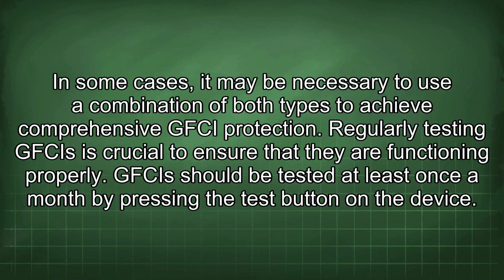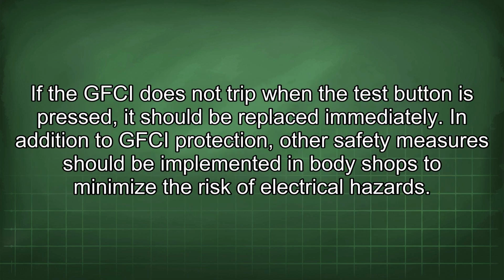Regularly testing GFCIs is crucial to ensure that they are functioning properly. GFCIs should be tested at least once a month by pressing the test button on the device. If the GFCI does not trip when the test button is pressed, it should be replaced immediately.